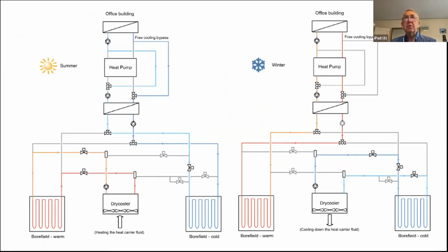But this is much different in that even though it has something called a dry cooler, and I'll explain, a dry cooler is nothing more than an air to liquid heat exchanger. It's got a fan. It's the same thing as the radiator in your car. It's got water or antifreeze solution. It blows air across the fins and tubing inside of the device. And so heat from the air will be transferred into the water or antifreeze, or cold air will transfer cooling there. So it's bidirectional. The word cooler is really a misnomer. It's an air to liquid heat exchanger, whether it's doing cooling or heating.